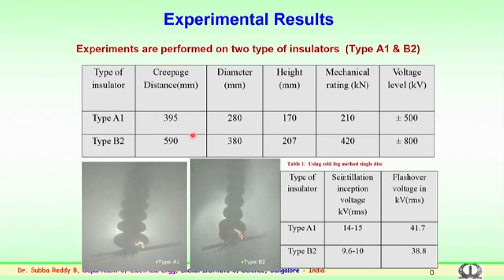So, these insulators are picked, and single, 3 and 6 insulator discs in a string are experimented on in the lab. Similarly, for the other type from a different manufacturer, the creepage length is 590 and the disc diameter is 380, a very big disc with a height of 207 and a mechanical strength of 420 kilonewtons. These insulator discs are used for plus minus 800 kV HVDC systems in the country.